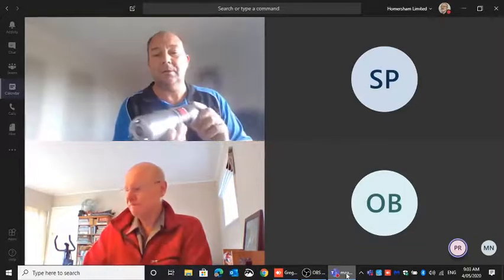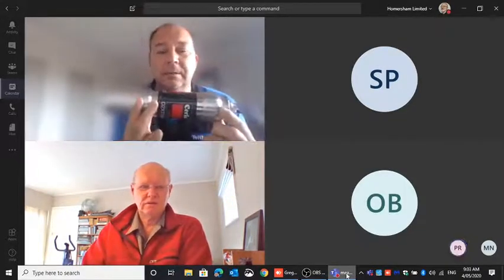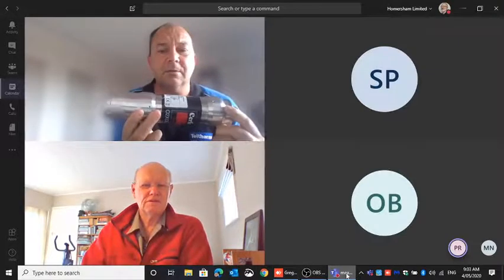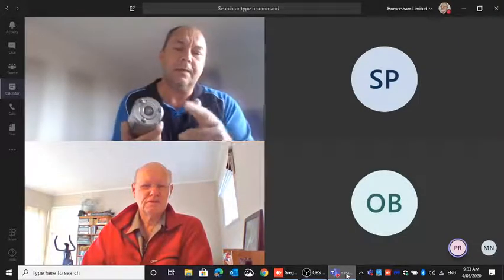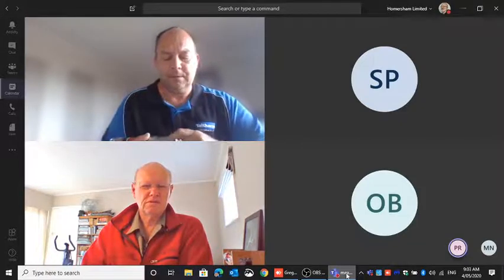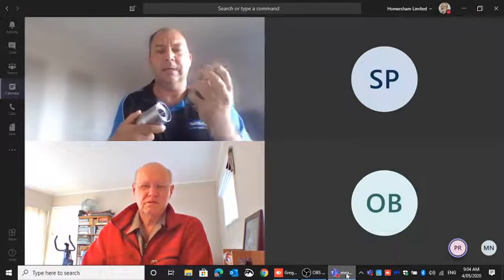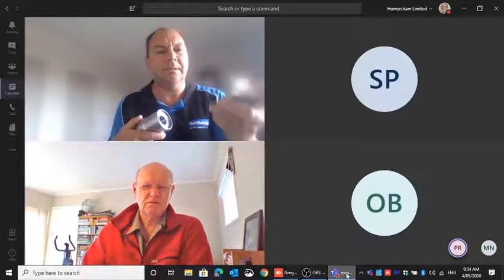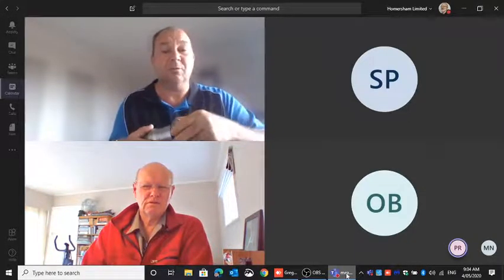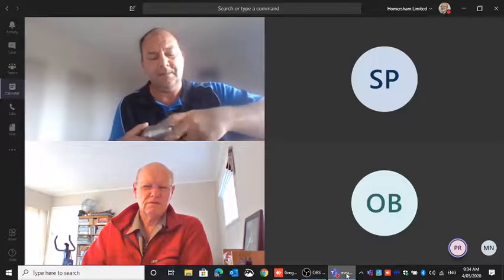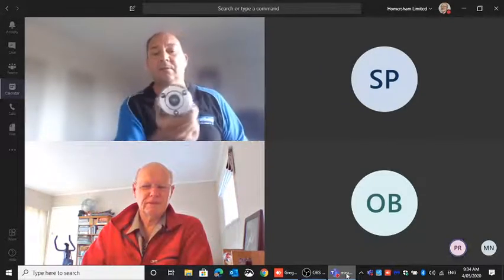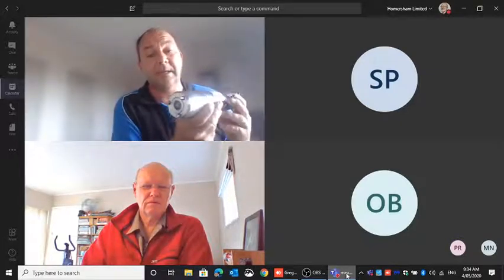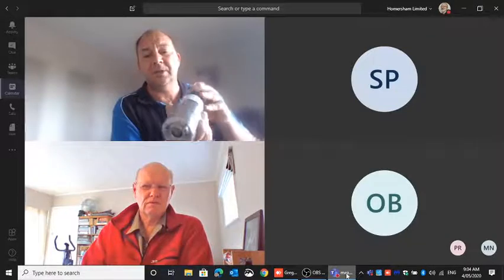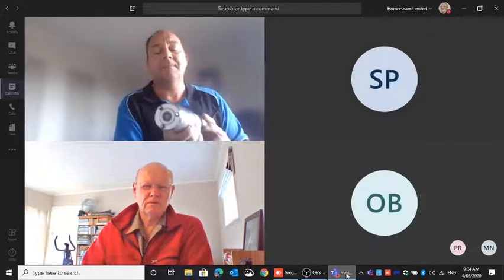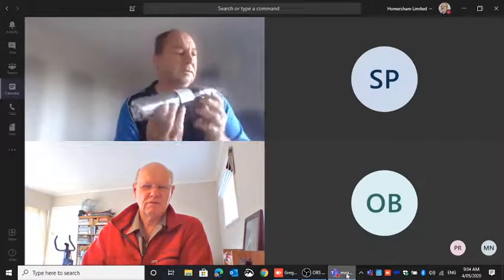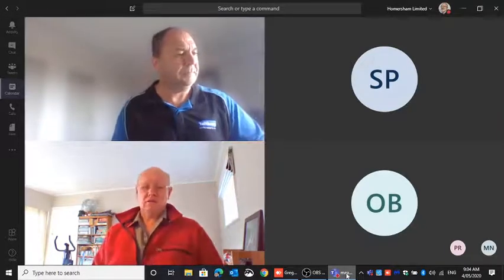Before we start, I'll show you the unit. This is the DO sensor. The solid sensor basically looks the same. Here you see the DO, with 3 points where we do the cleaning. If you want to change it, you basically plug the sensor out and put another sensor in. That could be optical or Clark cell. Screw it back on, hand tight, and drop it back into the water. That's how you replace a cell. For calibration, you just lift it just above the water and press cal. That's a DO sensor, full stainless, weighing about a kg.